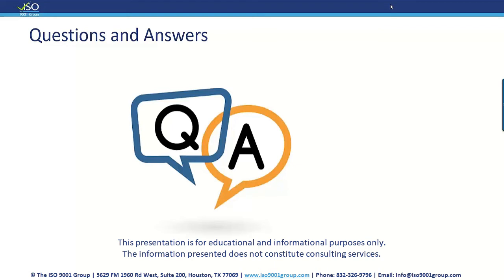Next question. Can we implement an in-house calibration program? If you're not a calibration laboratory, I would not recommend that you implement an in-house calibration program. That's why you need to verify your equipment, to check that it's reading properly. And if it's not reading properly, then we send it out to a calibration lab. So you don't want to become a calibration laboratory. That's not what we're encouraging. I'm encouraging you to verify your equipment. And if it's reading properly, don't send it out for calibration, because you're wasting money and time.